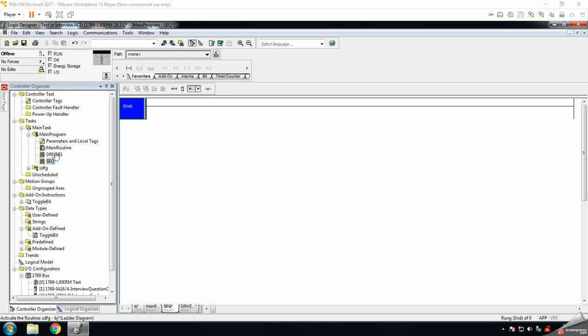So typically we have two sections in the PLC. One is driver and one is sequencer. Maybe it's not exactly the same name, but that's the name I'm using here. The sequencer is obviously the sequence section, and the driver section drives a physical output or some communication, a message or data package over whatever communication protocol: EtherNet/IP, Profinet, EtherCAT, RS485, or whatever. So let's try and keep it short and simple on our sequencer.